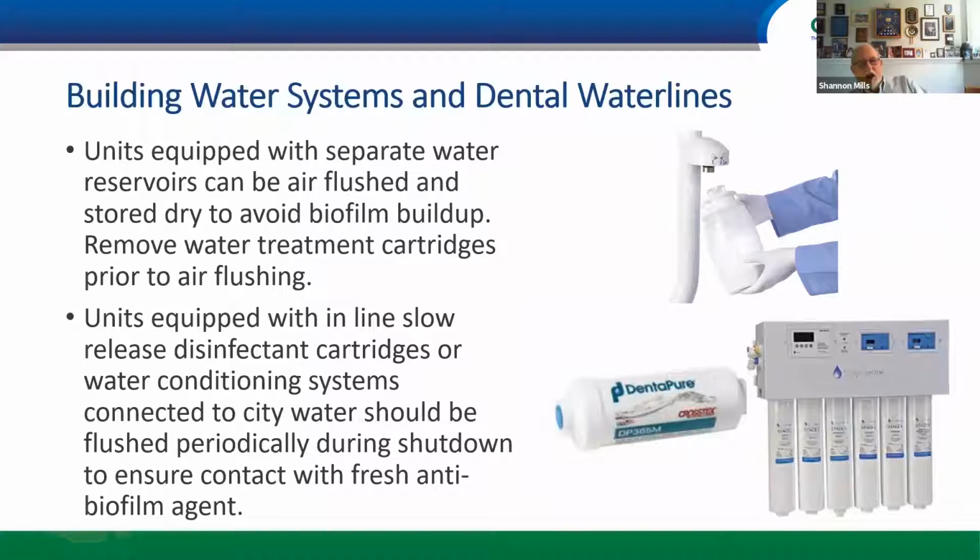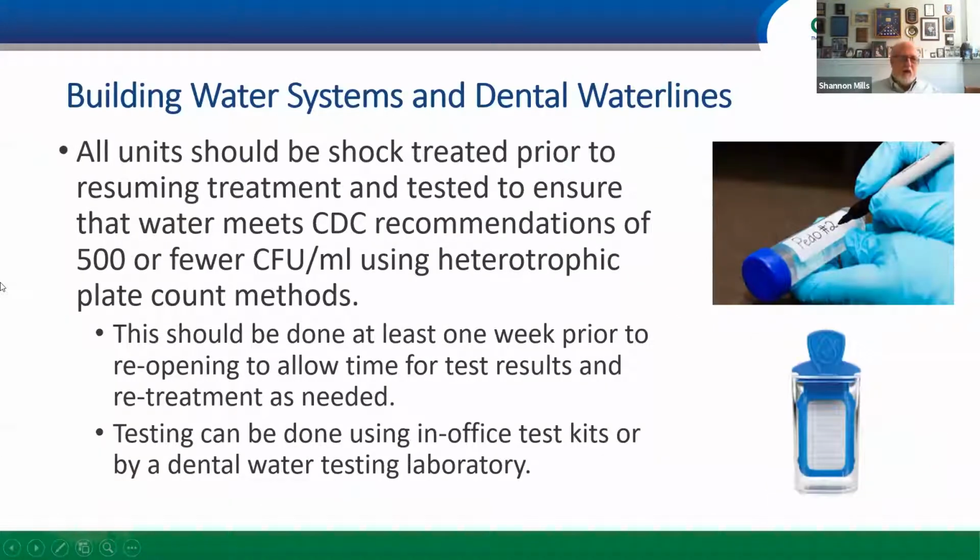If you have the products that have the cartridge systems or the conditioning systems, like DentaPure or Sterilex, you need to probably have been, and now go in and run the units periodically to make sure there's a residual germicide in there to control biofilm formation over time. Now, what the ADA says is to shock your units prior to resuming treatment. Totally agree. Follow the manufacturer's instructions, either of the dental unit or of the waterline product that you're using.